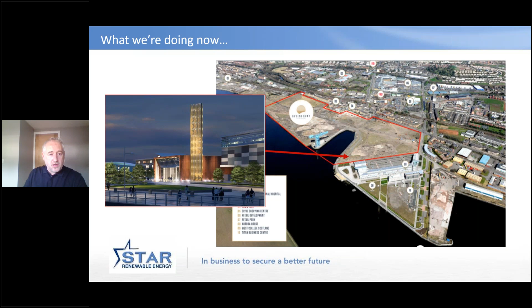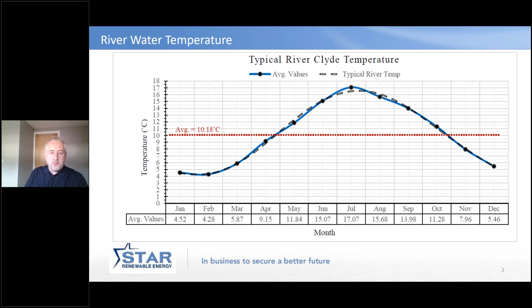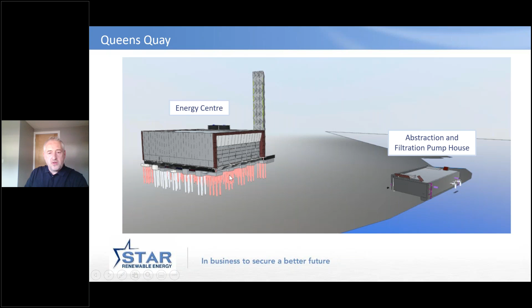So river temperature, why pick a river? Well, it's not the warmest thing that we could find. We could drill a hole in the ground and go much deeper and get heat at maybe somewhere between 20 and 40 degrees, but it's very, very predictable. It's also low cost. You can get the heat from the river without spending too much money. So what we're doing with the river is harnessing the fact that it's typically between 4 and 17 degrees all year, average temperature around about 10. And so we're taking that and cooling it down by about 2 or 3 Kelvin to give us that heat input into the heat pump. Pumping center next to the river, and energy center over here.